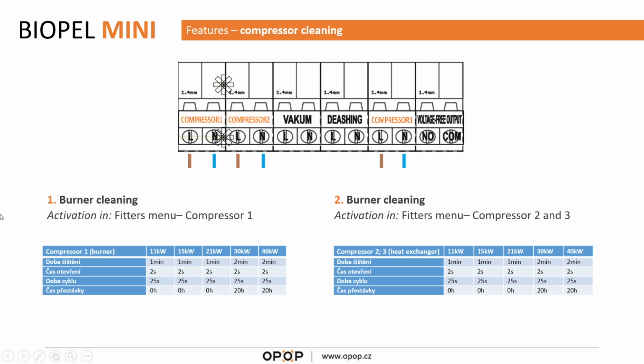So to explain these pre-selected values from the factory, there is a total cleaning time which is usually 1 or 2 minutes, bigger power, longer cleaning time, and then you have opening time for the solenoid valve. So within 1 minute the solenoid valve will open for, let's say, 2 seconds, then it waits 25 seconds for the compressor to build the pressure up again, and then it will again open for 2 seconds, and it cycles like this for 1 minute.